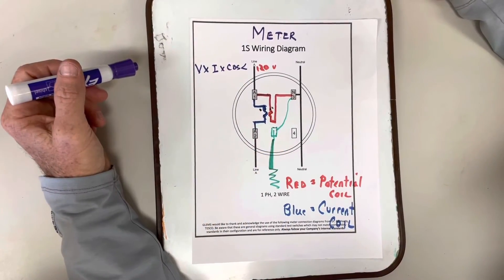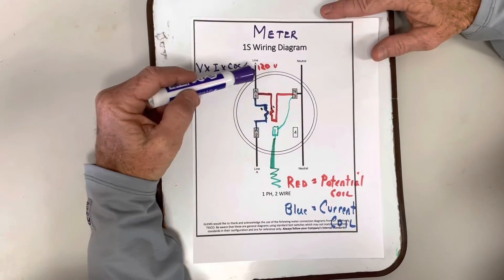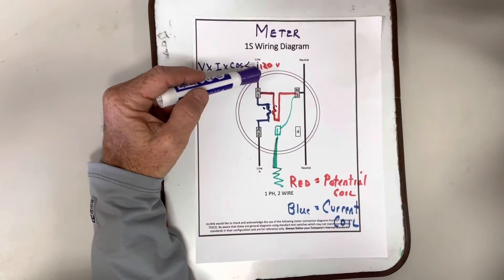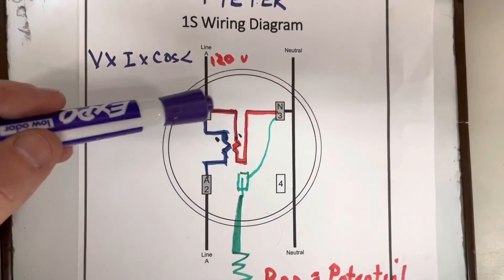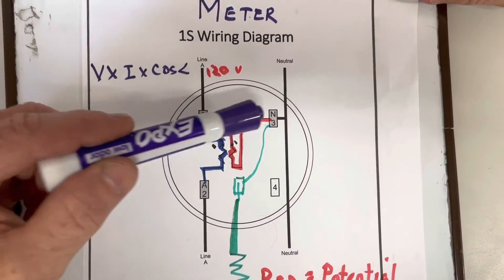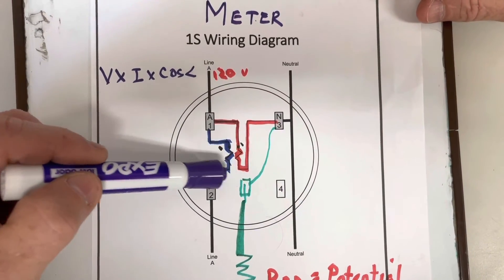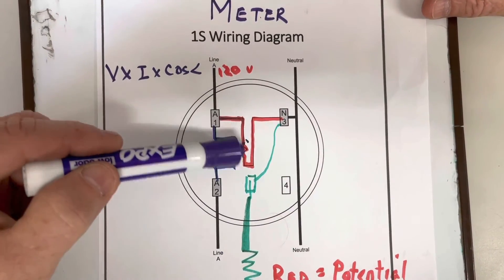And this 1S meter is wired this way. We have a current coil and a voltage coil. This voltage coil is rated for 120 volts. So it needs to go phase to ground. And this current coil is just measuring the current that's going through the meter.